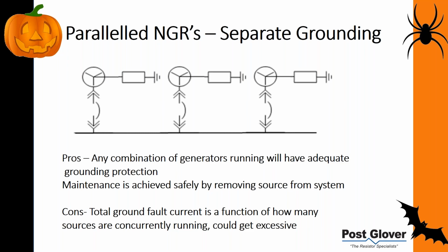The good news is, no matter what you do, if you have one generator, two generators online, or all three, you're going to have some form of ground fault protection. So you don't have to worry about what configuration you're using in terms of how many generators. Maintenance is also achieved, because if you took one generator out with its corresponding resistor, the others, as each source has its own protection, you're good to go. It doesn't really matter if you have one offline—it's not tied together, so you're able to safely maintenance that as well.